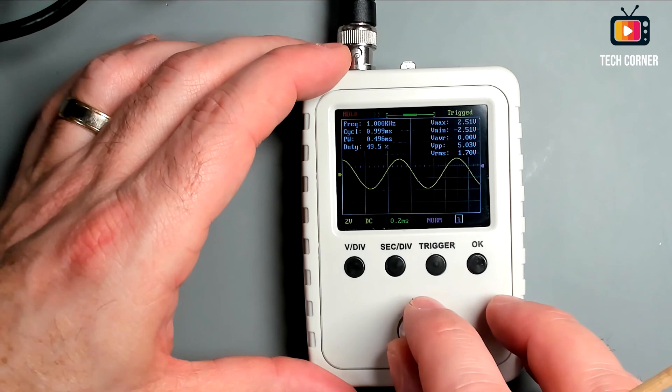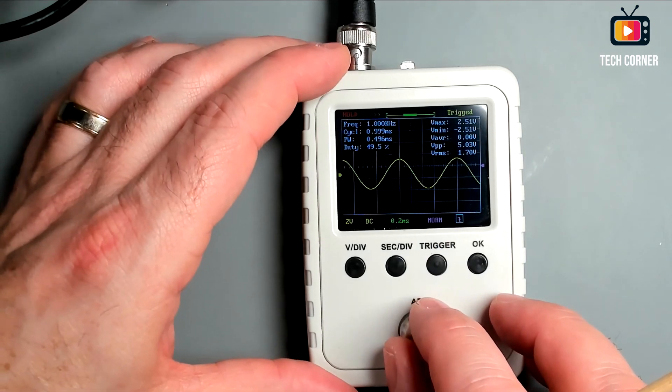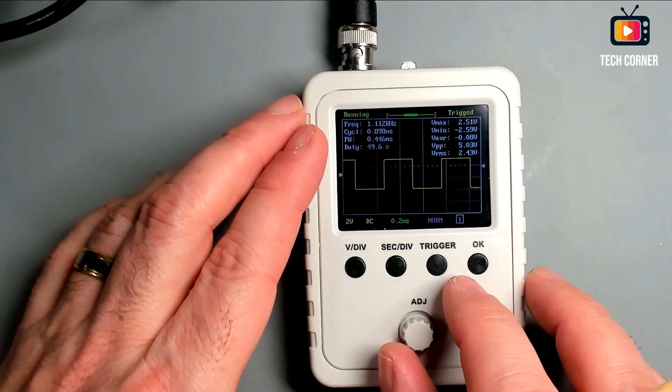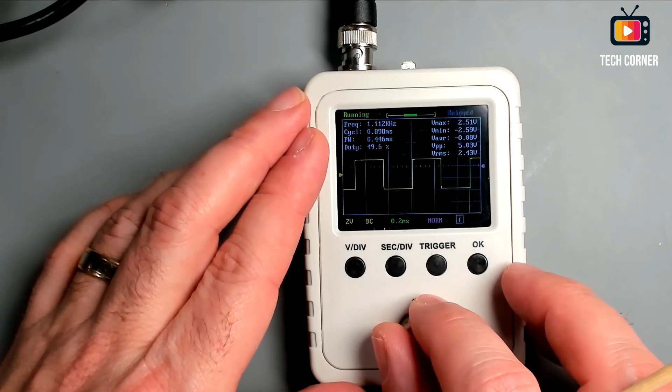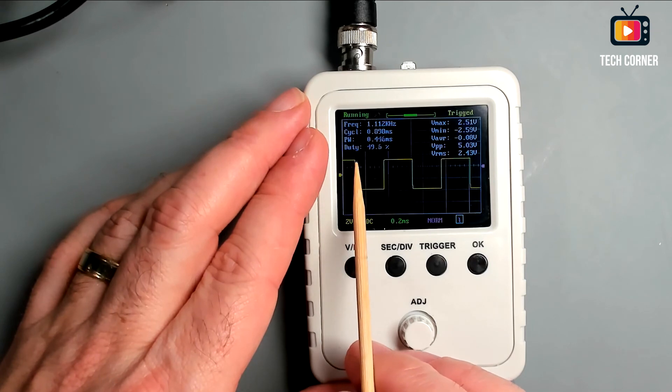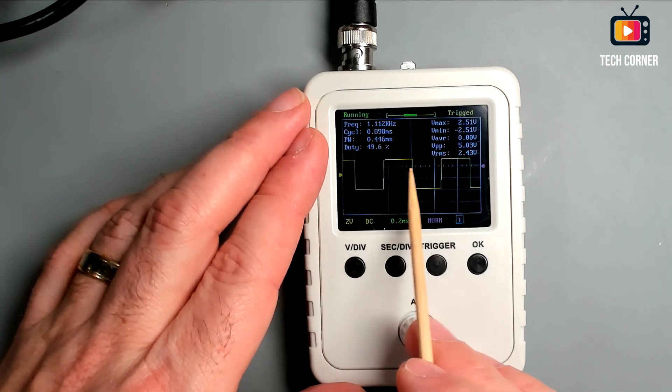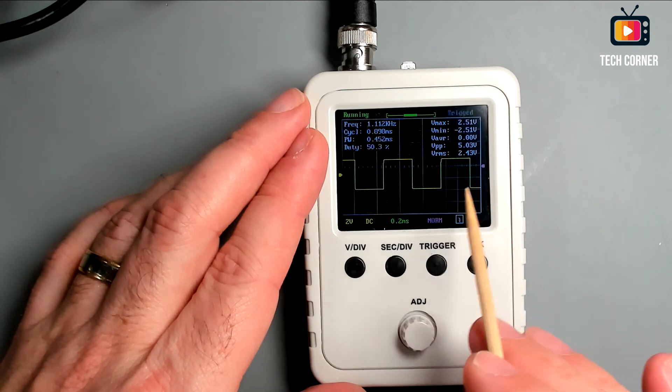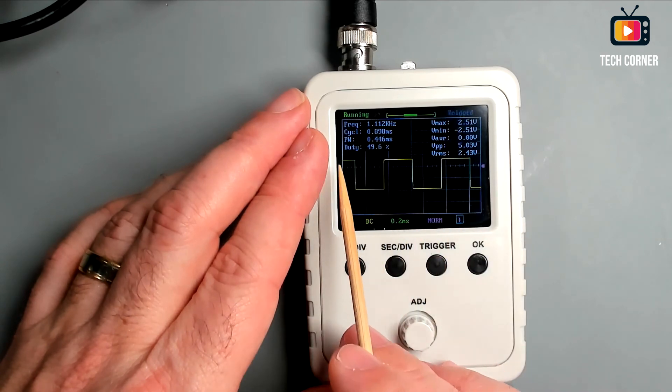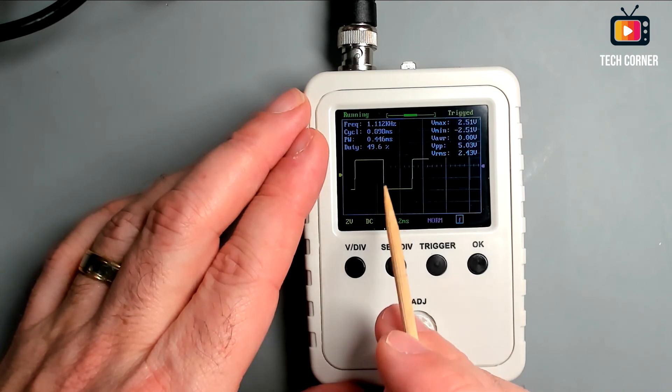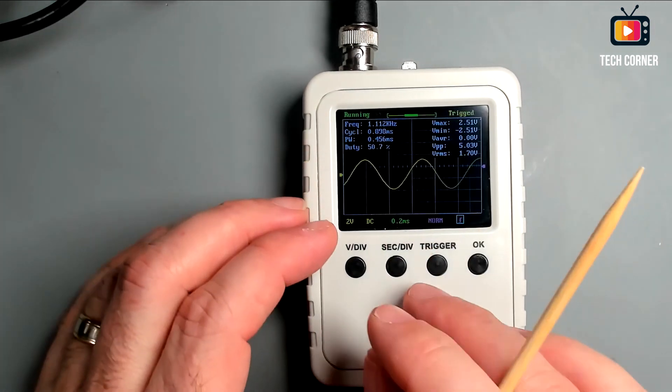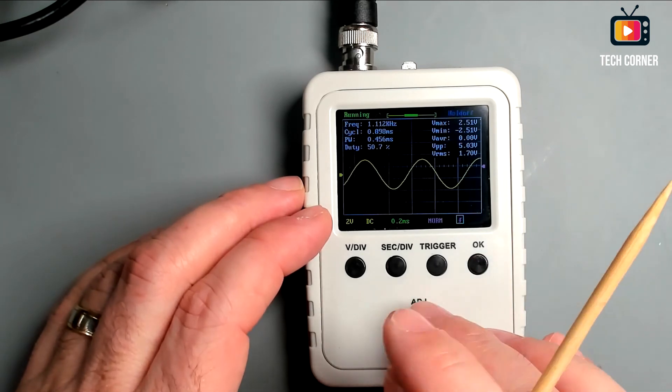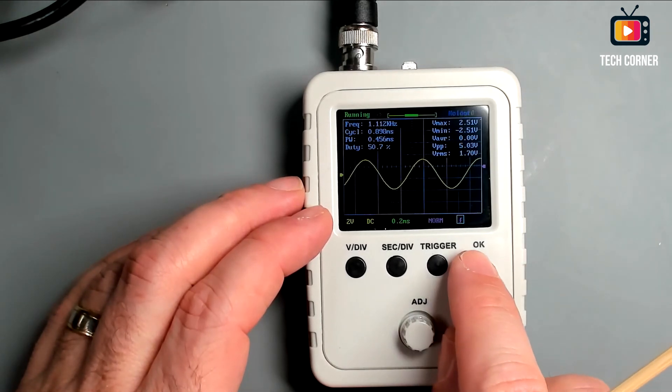Still on trigger, we have this small option that allows us to change the orientation of the line. So right now we have the signal starting at two and a half positive volts. And when we use the adjust knob, we can change the signal to start at two point five negative volts. So it will start off and then on.